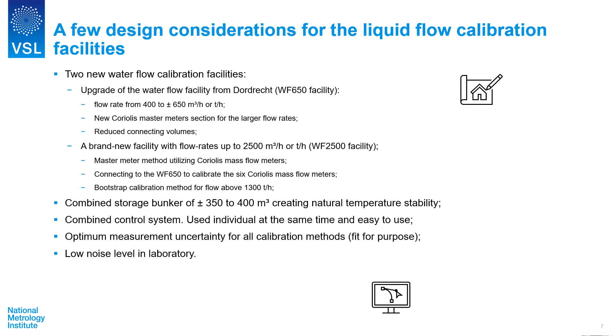The facilities have a combined storage bunker of approximately 350 to 400 cubic meters, creating natural temperature stability. They have a combined control system that can be used individually or at the same time and is easy to use. We will go for optimal measurement uncertainty for all calibration methods, fit for purpose. So that means that we will not maybe go to the ultra low measurement uncertainty, but something that we can produce on a daily basis. And we like to have a low noise level in the laboratories.